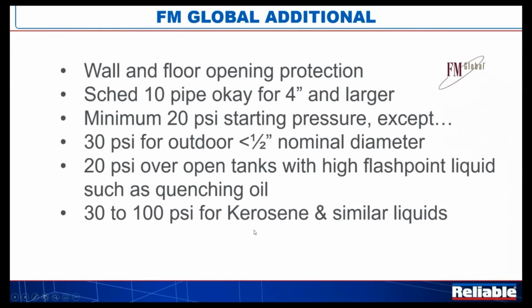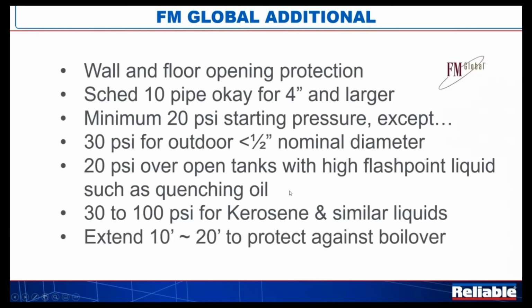30 to 100 PSI for kerosene and similar liquids. These might be like your cleaning solutions that you're rolling materials in and out of. We've got to make sure that we protect against fires with those. And then finally, with these pool fires, FM would ask you to extend the protection scheme 10 to 20 feet beyond the outer edges of the tank in case it boils over and starts running across the floor. So those are just some additional FM requirements. So now let's talk about some reliable products.